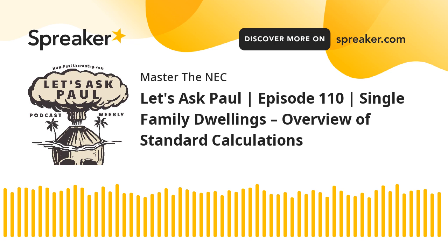Now, in the 2020 code, it proceeds to tell us that. Now, when I told you earlier about the dimensions, where do we get the dimensions? Where do we get the floor area? Where are we pulling that information from? Well, the instructions come in 220.11. Now, if you go look at 220.11, which used to be in 220.12, but it's 220.11 in the 2020, it says the floor area for each floor, now, if you've got more than one floor, like a basement and a first floor, each floor, it says, shall be calculated from the outside dimensions of the building, dwelling unit, or other areas involved.